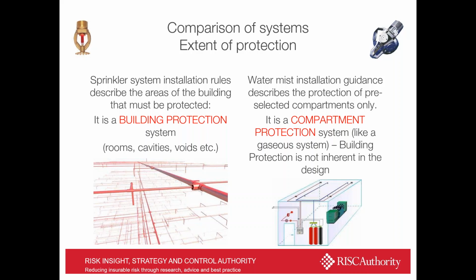But when you specify a water mist system, it really is for compartment protection, and generally it's down to the user to determine what areas, what subcompartments of that building should be protected. So there is a key difference there. If you see a sprinkler system in a building, you'll know that if there are voids over a certain size with combustible content, the sprinkler system will be running in those invisible places too. The same is not inherently encompassed in water mist design by default.